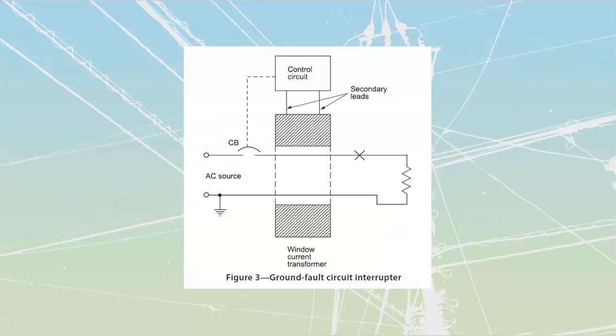Let's talk about another really cool use of instrument transformers. We know all about ground fault circuit interrupters, GFCIs. These are different than the AFCIs, the arc fault ones. Arc fault ones are looking at current that they are going to be trying to monitor. We are looking at the amount of ground fault current or escaped current that is not coming back. We know that ultimately KCL should be met, Kirchhoff's law of current, which states that the sum of all currents that are going to go and enter a circuit should go and leave that exact same circuit.